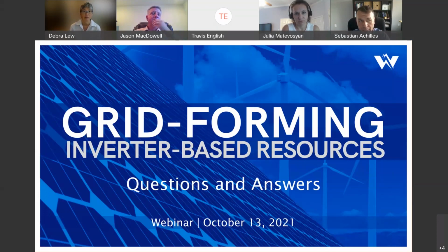A separate aspect I think is very important - sorry to repeat this - is that things are getting more complicated, with more and more plants close to each other. So you're evaluating your new plant, and now you have like five plants around it. They're not exactly next to it, they're far away, but not too far away. This is really challenging us, and I don't have a good solution for that problem. In general, calculating short circuit ratio while ignoring adjacent plants is not recommended - that will give you a very optimistic result. Calculating short circuit ratio ignoring neighboring plants and asking the manufacturer if that's okay may lead to not detecting or masking problems. So it's necessary to have short circuit ratio estimations that account for the presence of plants close by.